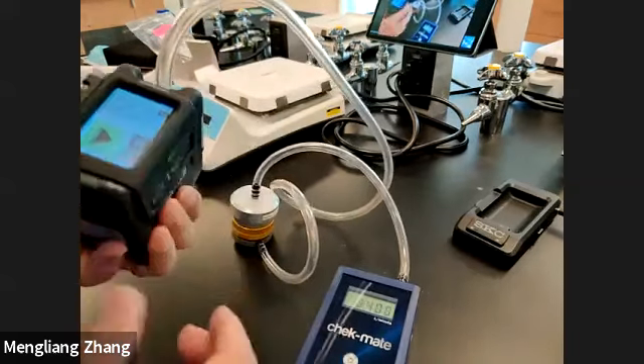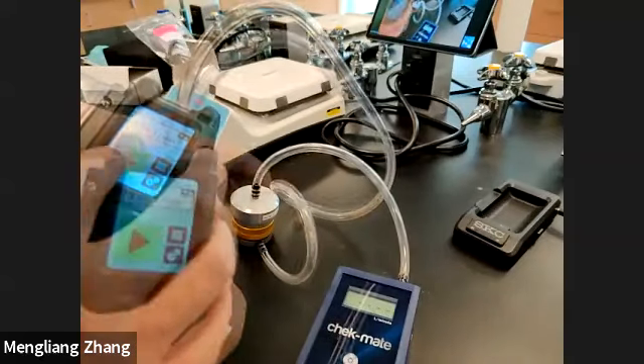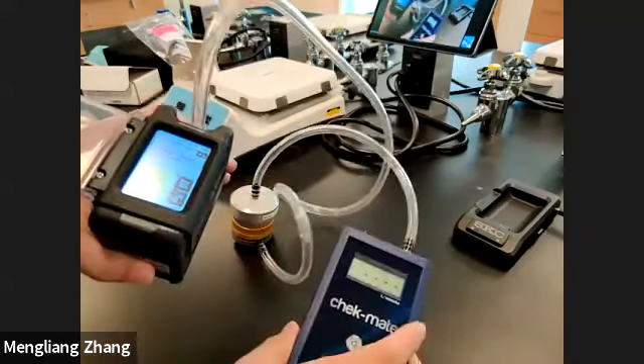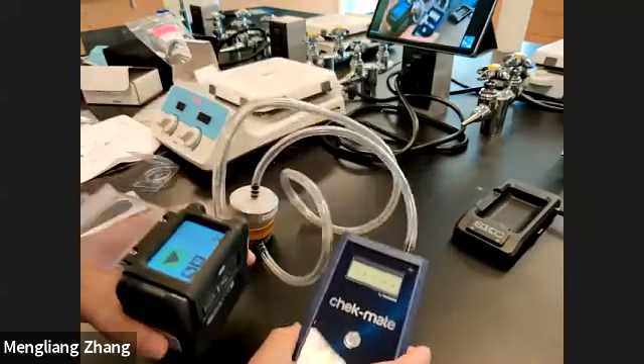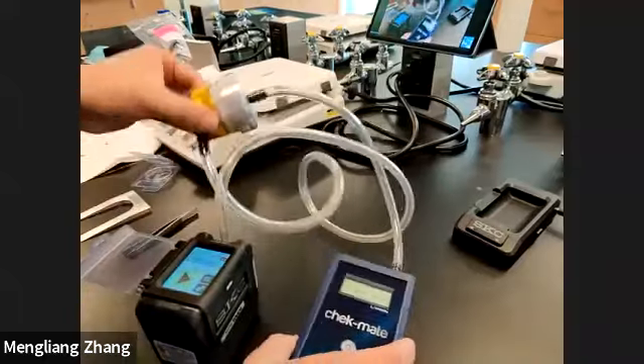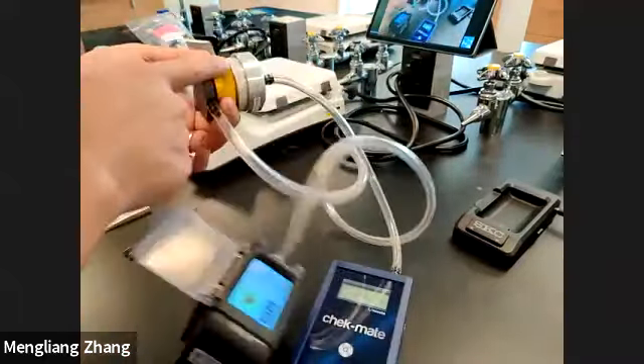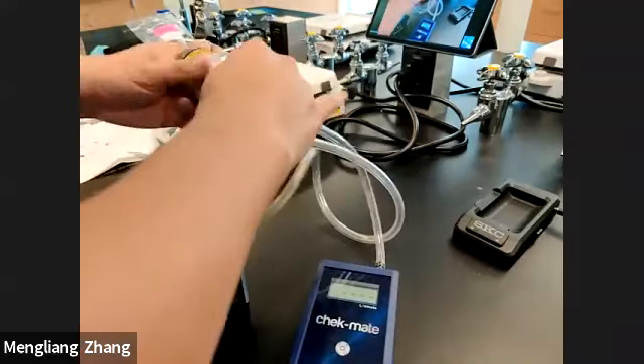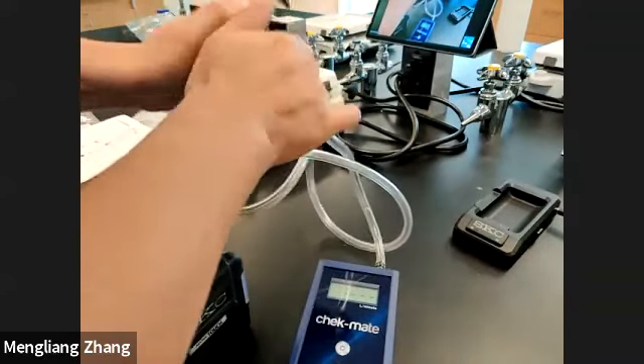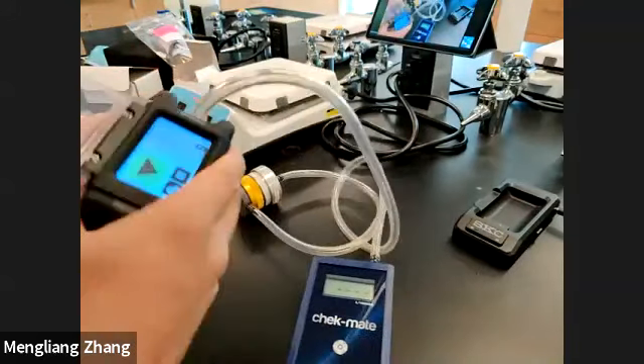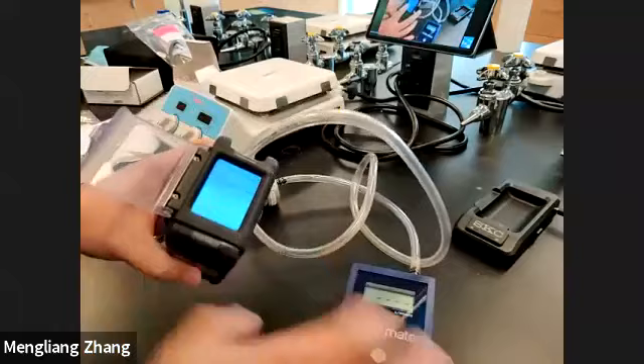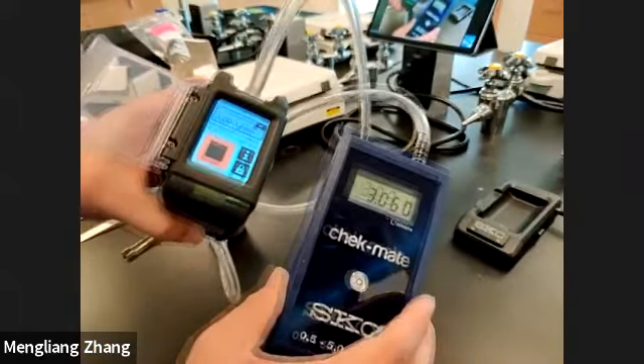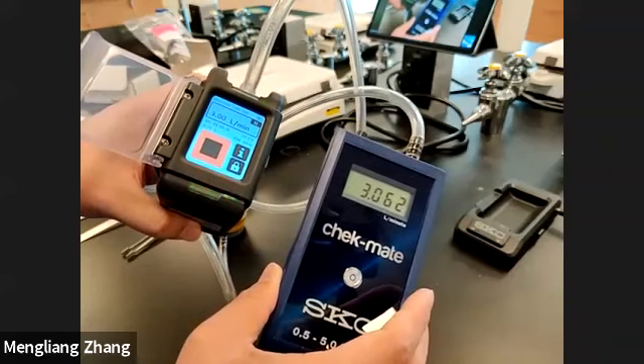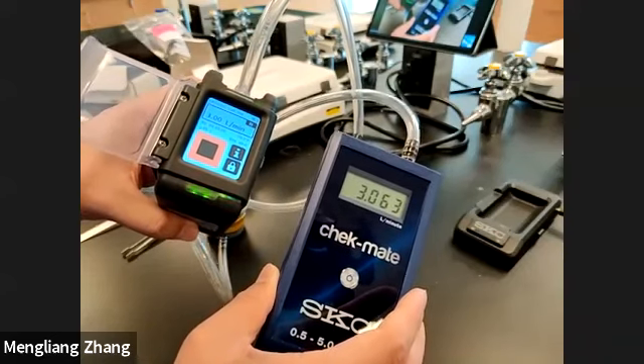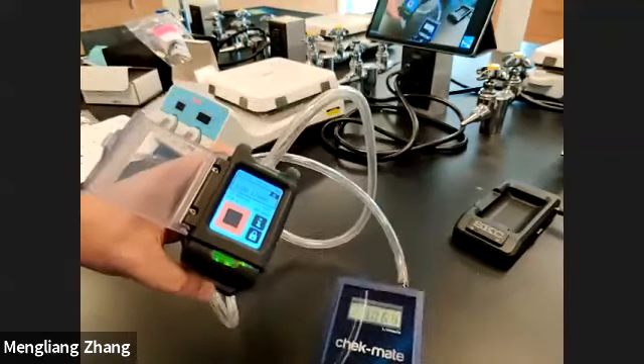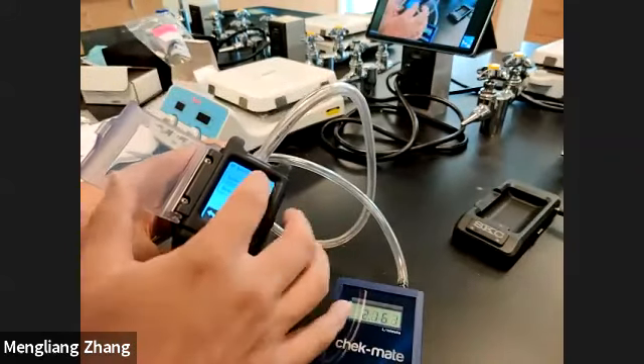In the previous calibration, even with the maximum adjustment factor, the real flow rate from the calibrator was still not 3.0 liters per minute. So what I did is check if there is any leak from the impactor and the connections of tubing, and we secured the impactor again, and then I checked the flow rate again. After I secured all the connections, the real flow rate is more than 3.00 liters per minute. So in this case, I need to recalibrate this.